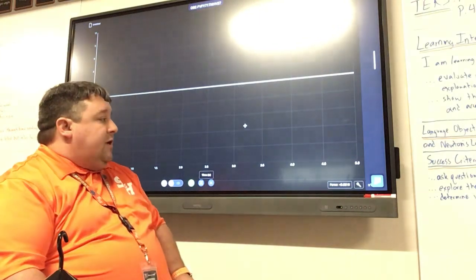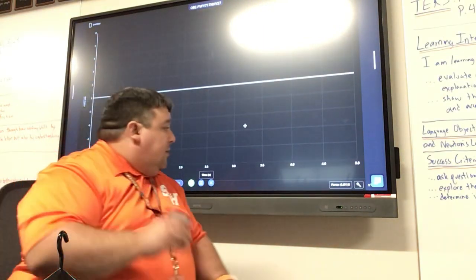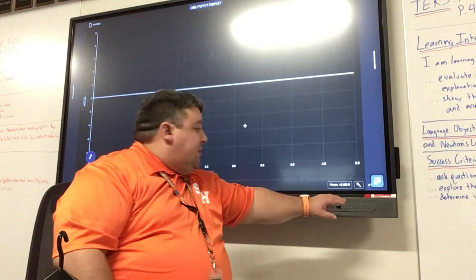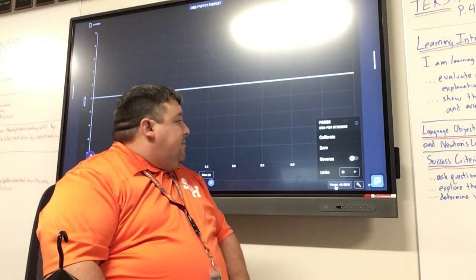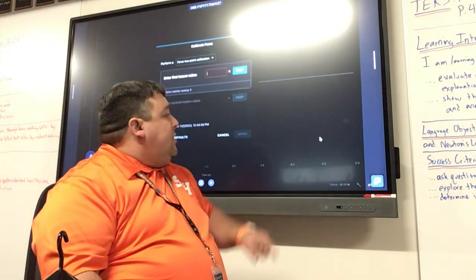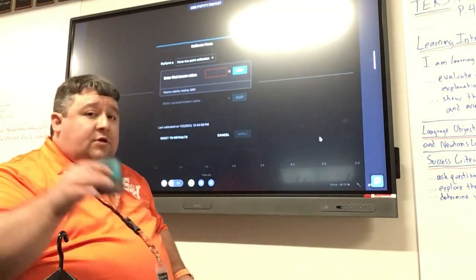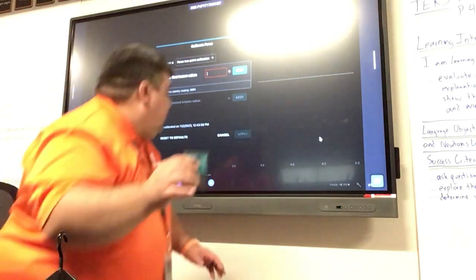And then we need to change some things here. So again, we need to calibrate this thing. So down to the bottom here where it says force, you're going to tap that and then calibrate and zero. We're going to do both of those. We've got to do calibration first. So first things first, just as is with zero newtons of force on it. I'm going to go over to my keyboard and type that in.